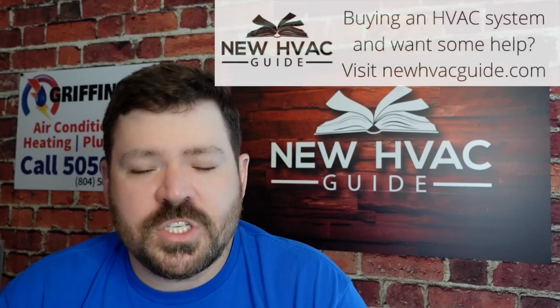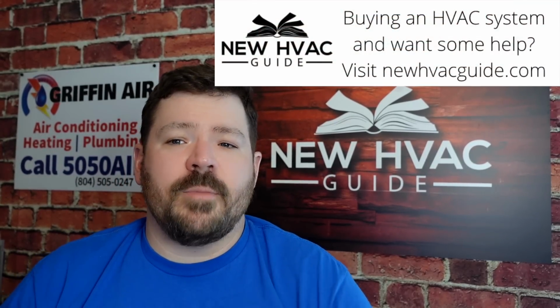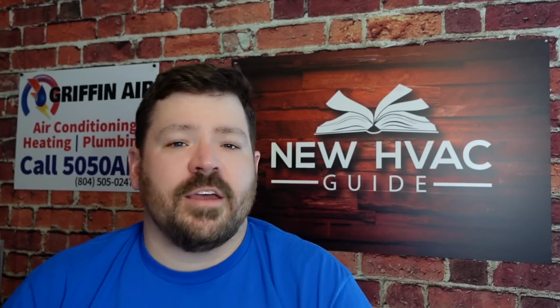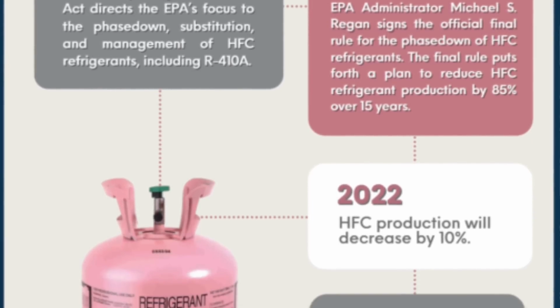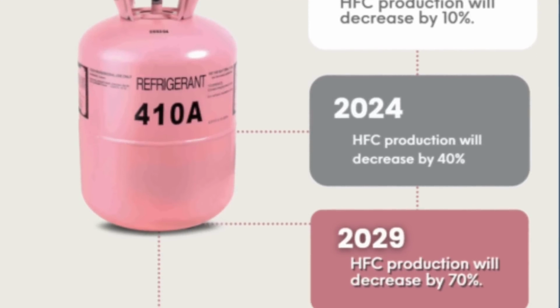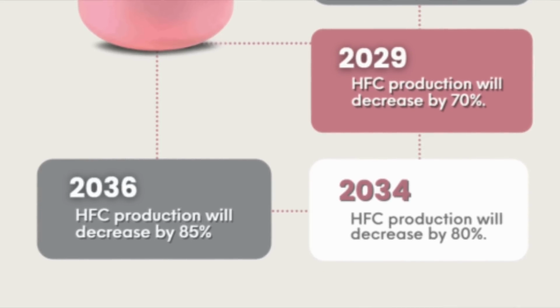And so here, just in the last couple weeks, we have an article that's come out talking about how the EPA has a proposed rulemaking dealing with the plans to ban 410A refrigerant. This is the first time with this whole phase out that we've had a specific timeline. I did a video where we talked about how this year we're going to phase out 410A by 10%, and then 3 years later we're going to be at this percent.